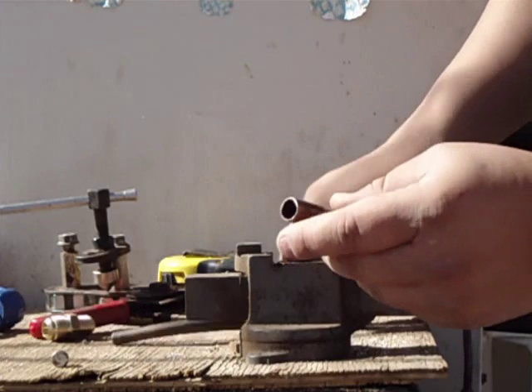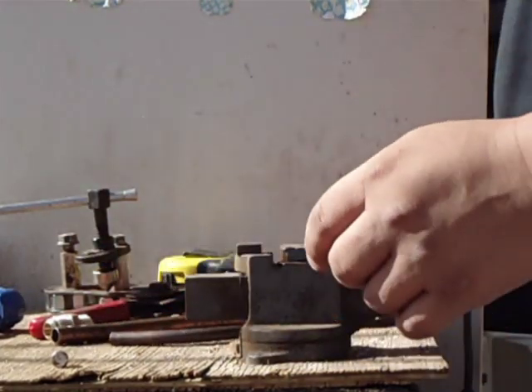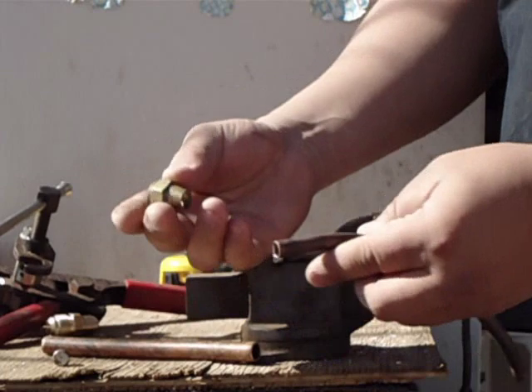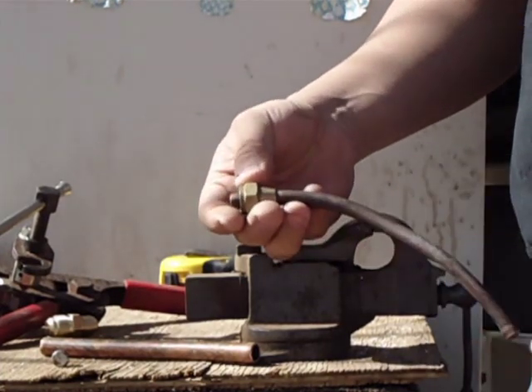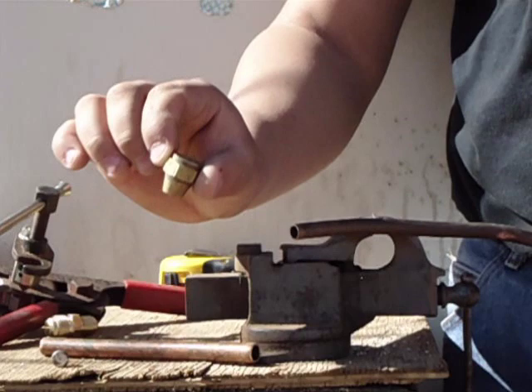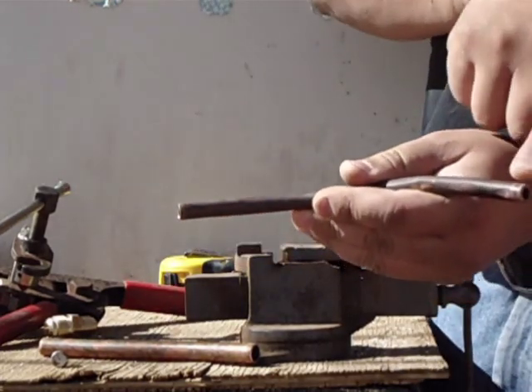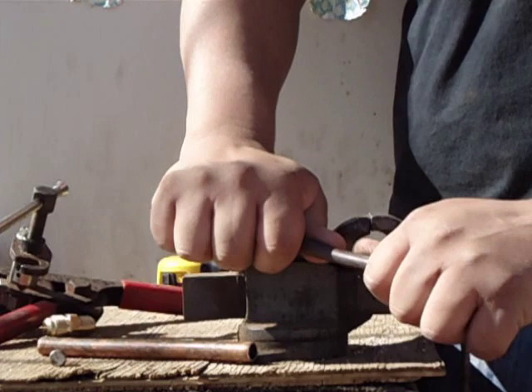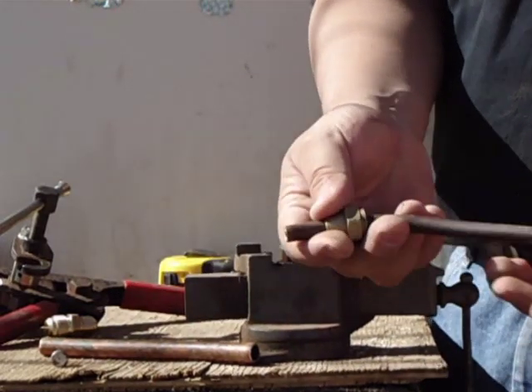What you're going to have to do — before you clamp it with your tool — is stick the fitting inside the tubing. Because once it's flared, you're not going to be able to slide it on, especially if the other side is already connected or already flared. So it is very important to do that first. If you have already a flare on one side, you're going to have to place the fitting that goes right there to the side that is not yet flared.